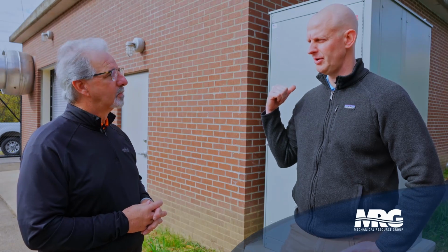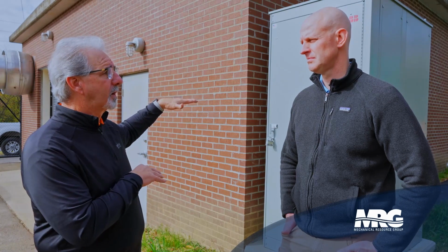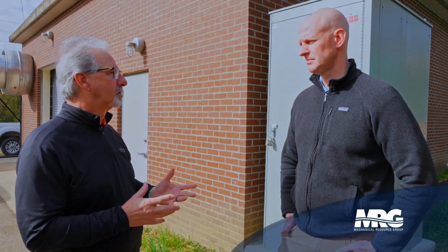So this automatic transfer switch is basically saying once we lose power from the utility, we're kicking the generator on, and we're going to do it as fast as we possibly can without interruption in any kind of pumping or motor or drive. Correct, because the SCADA system, no matter what, is on its own power supply, and it also has a battery backup, so it will never drop during that transition period. Even if we do have a problem negotiating the load between generator and utility, those run commands will stay there. The drives themselves are set up for an automatic restart. So even if I do fault, every 10 seconds I'm going to retry. As long as the voltage comes back up to a level that satisfies the drive, it will restart. We have them set up to restart into a coasting load. If that pump is still rotating, we turn on, negotiate with the rotor, and turn on at whatever speed it's actually spinning at. We can pick up what that speed is, match it, and carry it on from there.